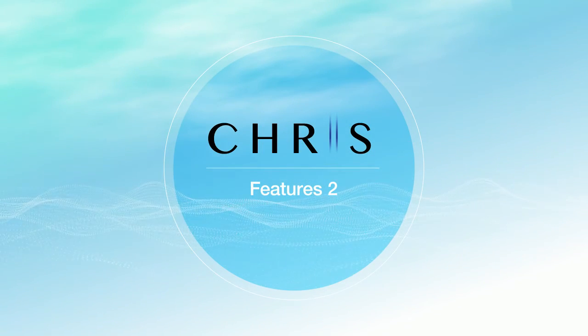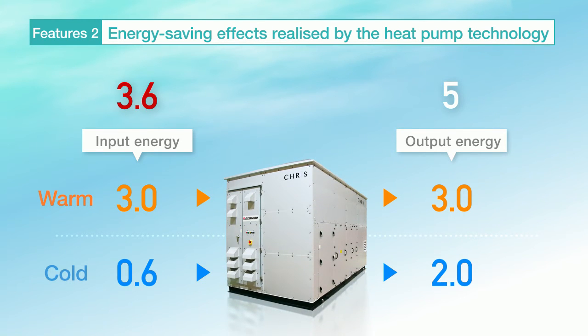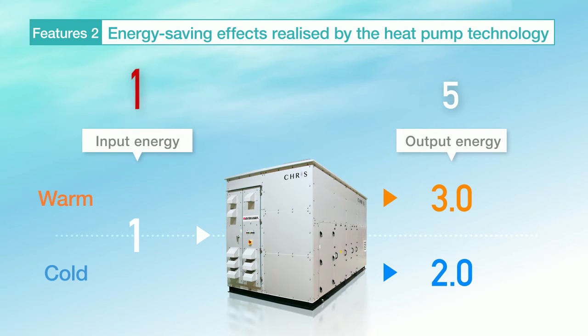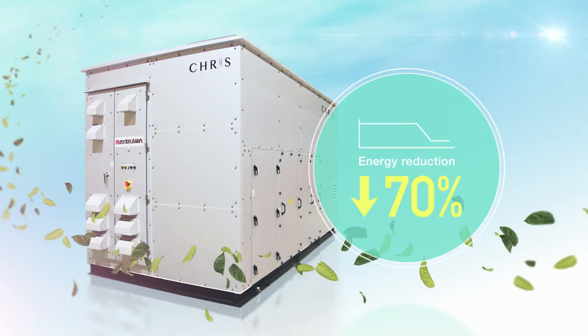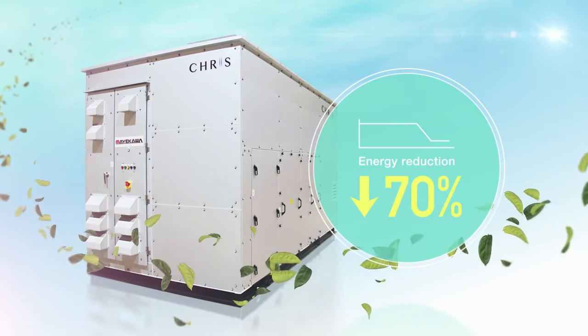Conventional desiccant dehumidifiers use electric heaters or steam as the regenerative heat source and also require an air-cooled chiller to control increases in temperature after adsorption, resulting in extremely high levels of energy consumption and high costs for the customer. On the other hand, because it uses the heat pump method, CHRIS is able to perform cooling and heating using a single unit, enabling greater energy-saving operation in low temperature environments — an environmentally friendly dehumidifier that reduces energy consumption by approximately 70%.